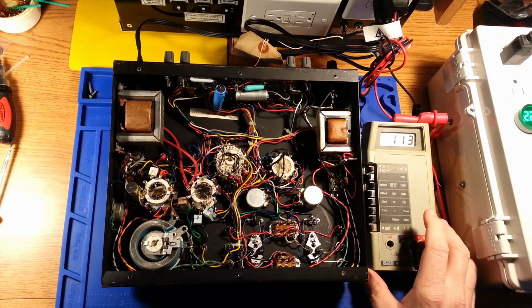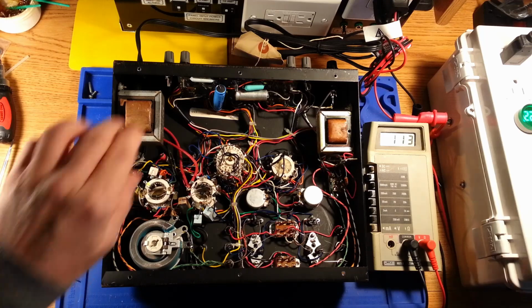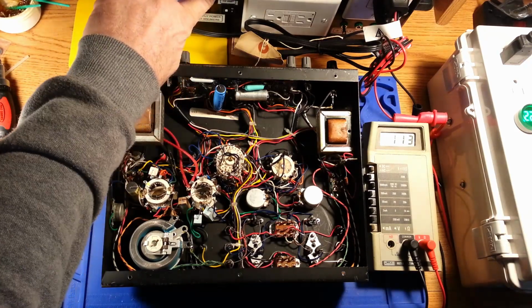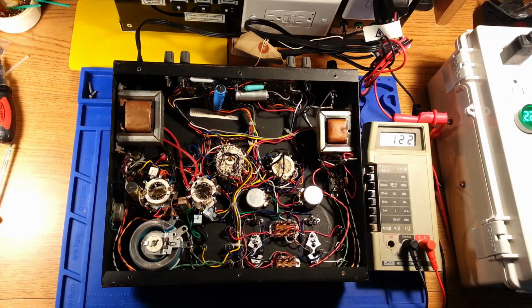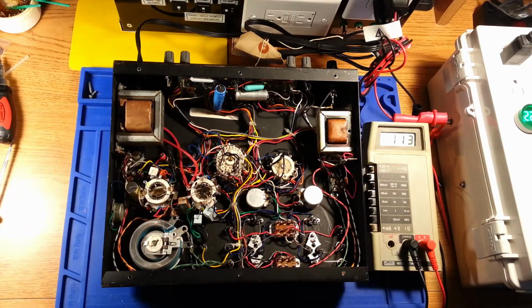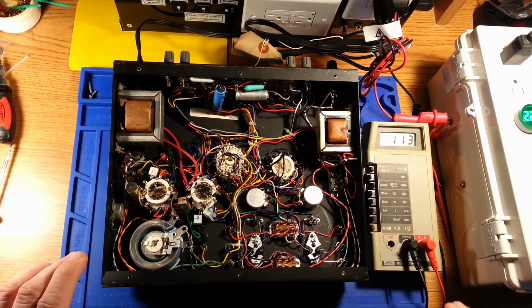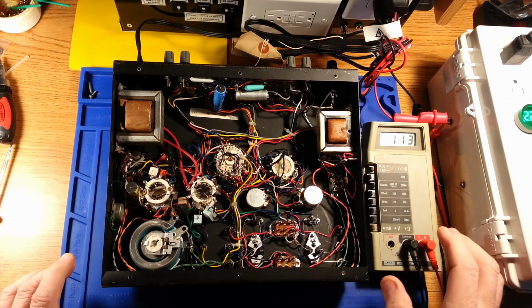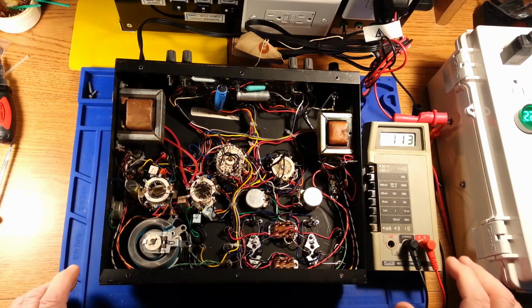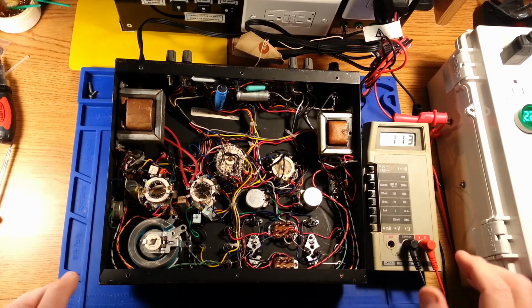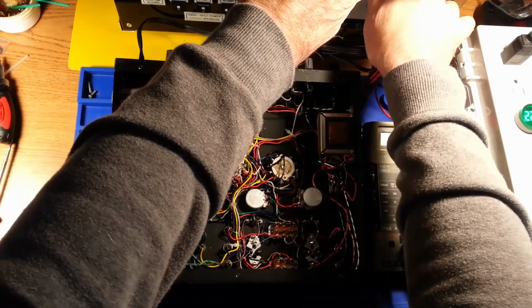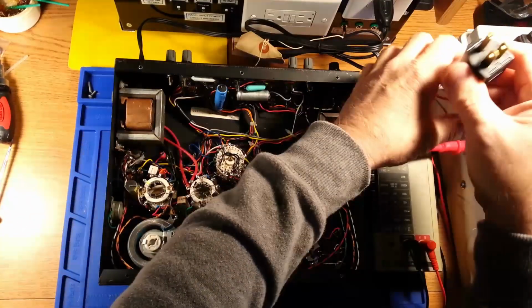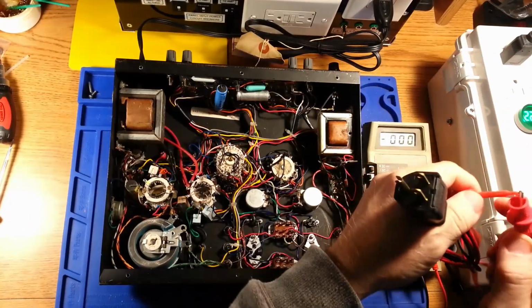I'm checking it. It's got a line voltage. If I go direct and bypass my dim bulb setups, I have 123 volts coming into my dim bulb panel. The meter is indicating 122, so I know it's got a good AC function on it. So right now I am limiting things with a 7 watt bulb. It's a very, very low level. It's basically just to check for signs of life. So I'm going to disconnect the meter from the AC output of the dim bulb tester.